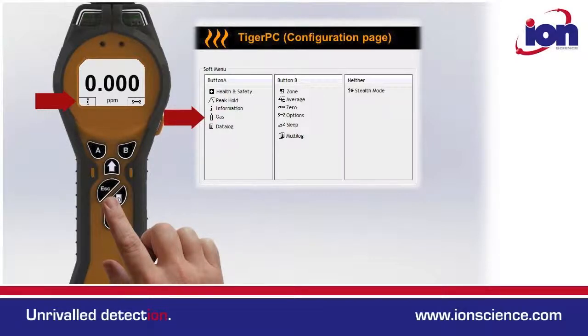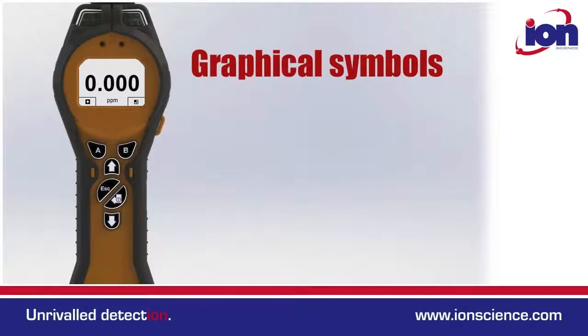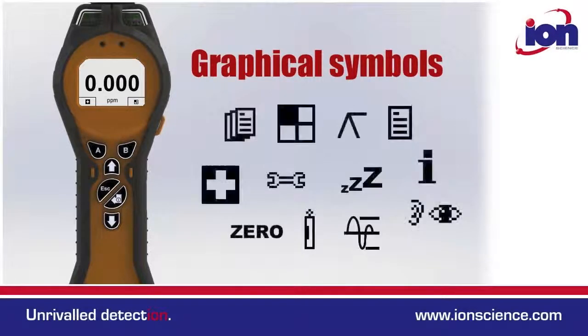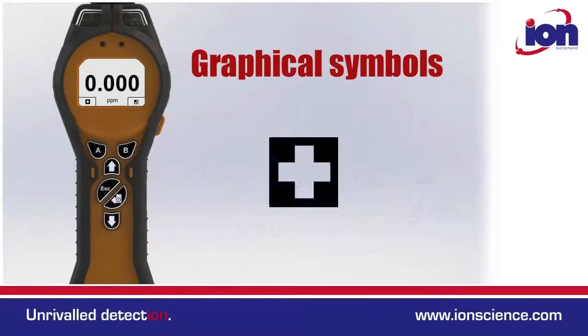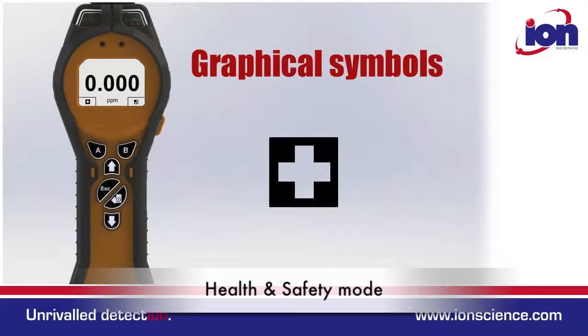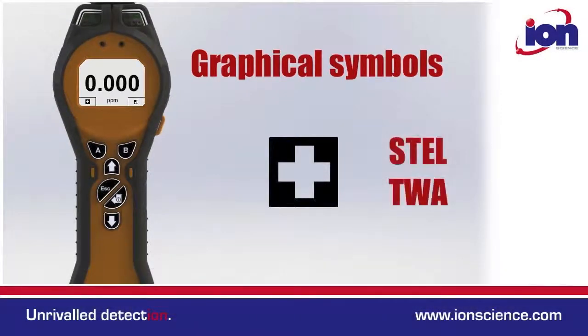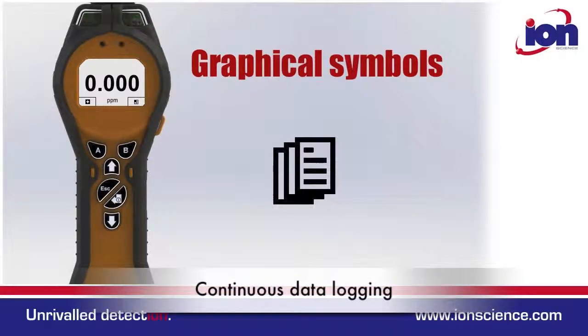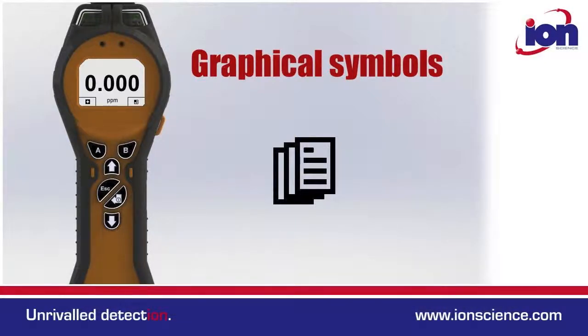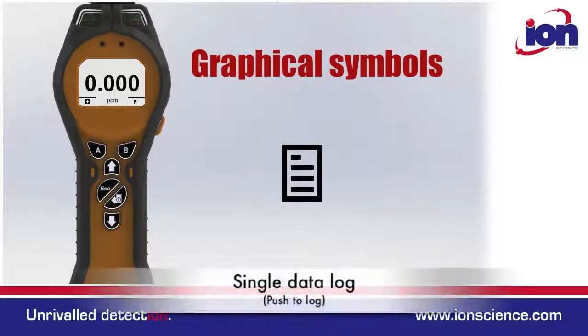The Tiger has a wide range of features represented by the following graphics. Health and safety mode: when selected, the Tiger calculates personal STEL and TWA exposure levels. Continuous data logging: when selected, the Tiger automatically data logs at the frequency previously set in Tiger PC.